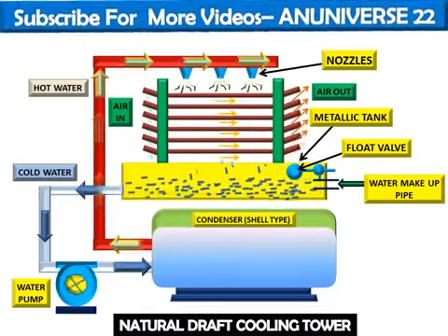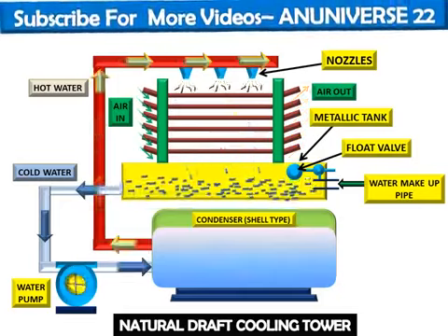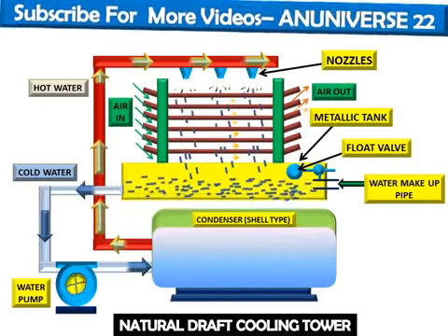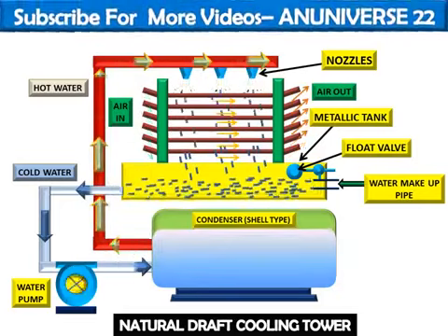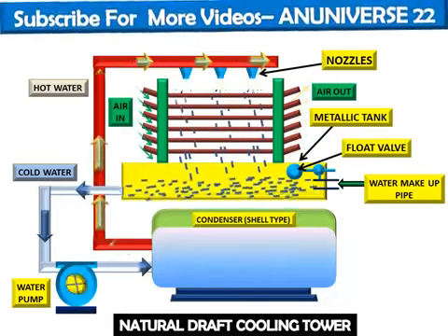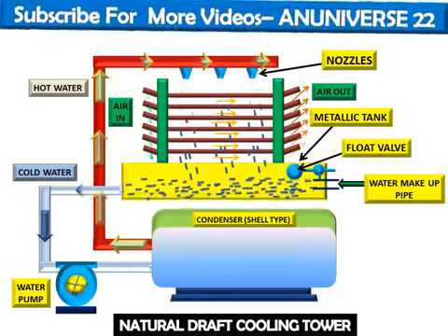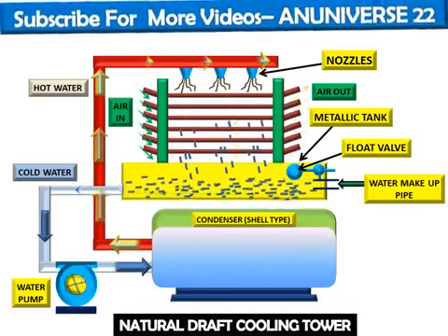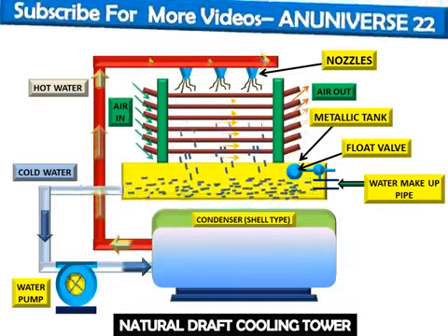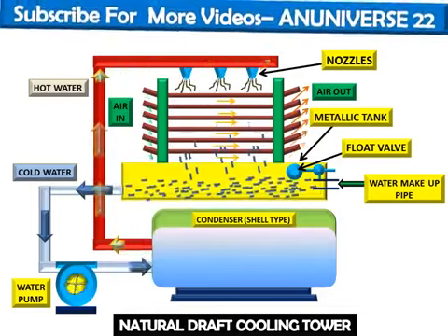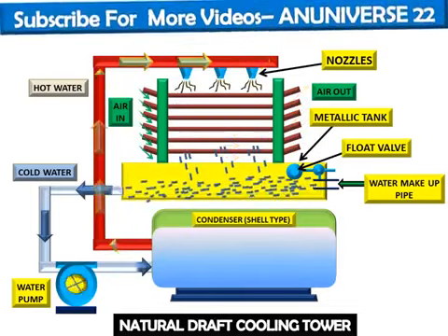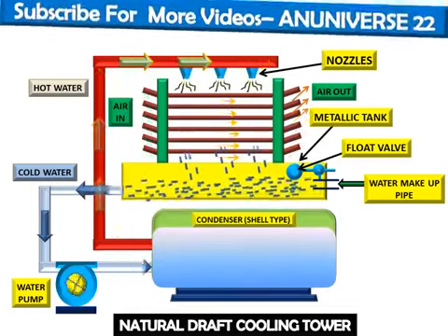It may be noted that the finer spray exposes more water surface to air. So if the spray is too fine, too much water is blown away, and the water spray blown away by the air is called drift. The drift increases water loss in the tower but does not affect the cooling action.